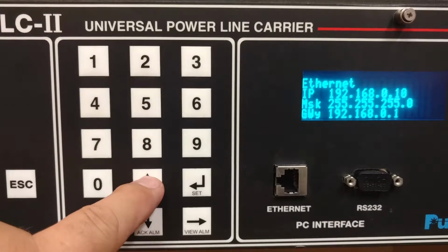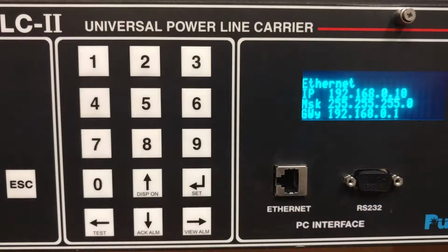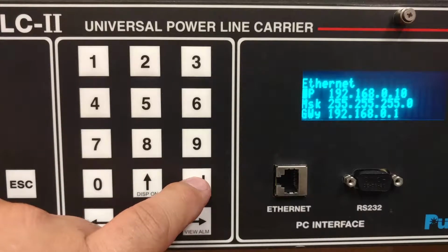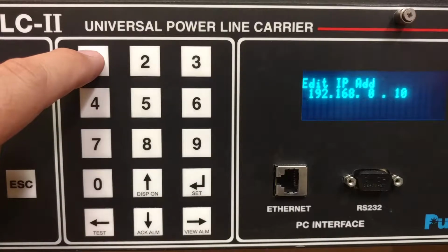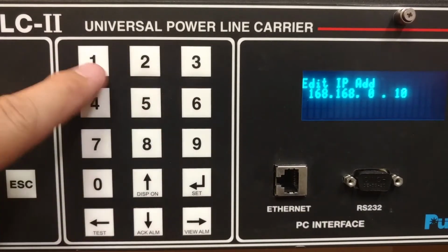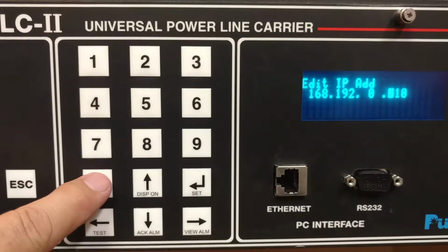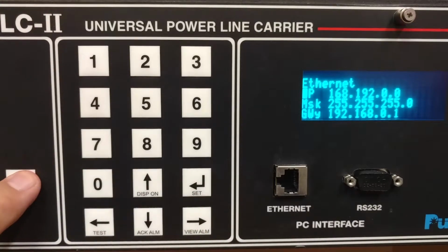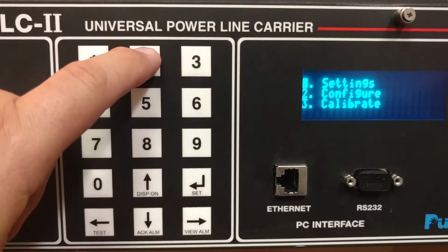If you are configuring this for your network, then your network administrator would provide you with this information specific to your network. To change any of these settings, use the cursor keys to highlight the setting, in this case IP address, and press Set. Then type the new settings with leading zeros. I will change the default IP to demonstrate 168.192.000.000. Then press Set again. When you are done, press Escape to exit. You will then get a "Please stand by updating settings" message, followed by a "settings updated" message.